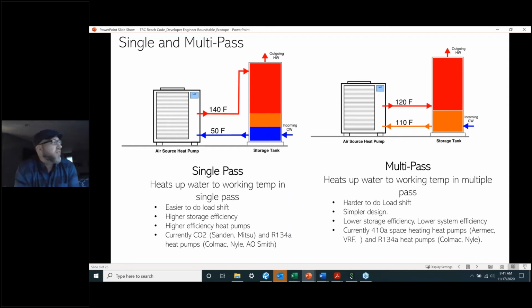That's a great question. Personally, we've done about 4 multi-pass designs and seen them in play. When doing multi-pass for the primary plant, if one of the heat pumps goes out, you can potentially lose the entire system because your recirc is still flowing through your tanks, stripping out all that heat. Whereas when you decouple it, you still have that primary storage.